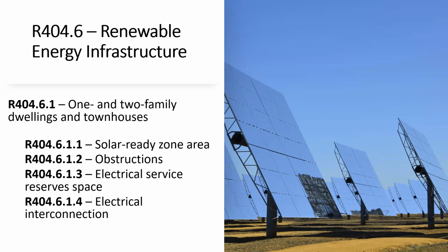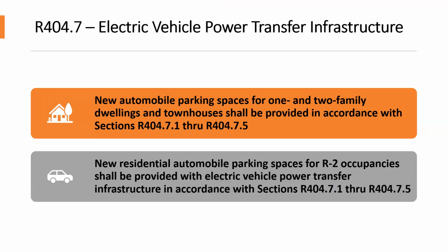And then electrical interconnection, it says the electrical junction box shall be installed within 24 inches of the main electrical service panel, shall be connected to a capped roof penetration sleeve or a location in the attic within 3 feet of the solar ready zone by a minimum 1-inch non-flexible metal conduit or permanently installed wire as approved by the code official. Where the interconnection terminates in the attic, the location shall be no less than 12 inches above ceiling insulation. Both ends of the interconnection shall be labeled for future solar electric. So they're identifying those requirements for those spaces, and how those are going to be handled for residential.